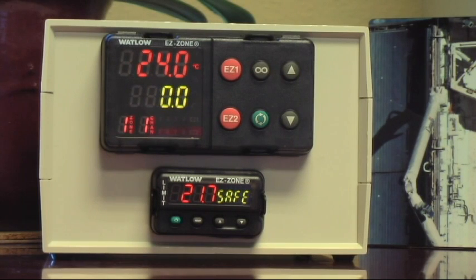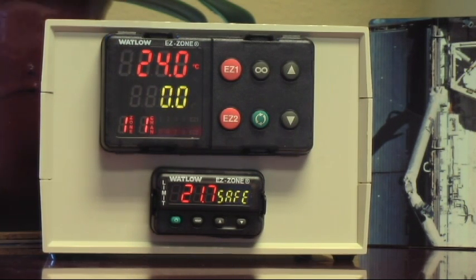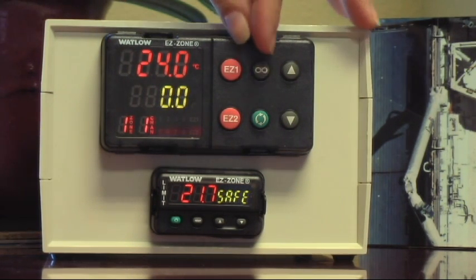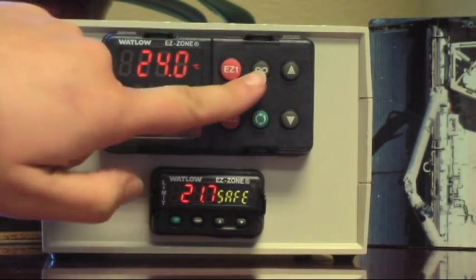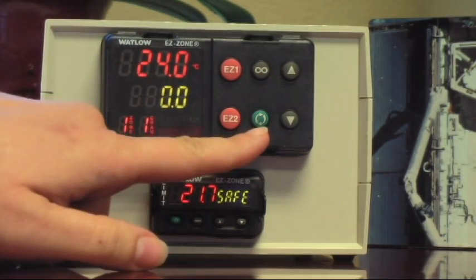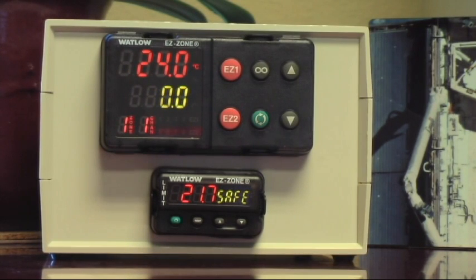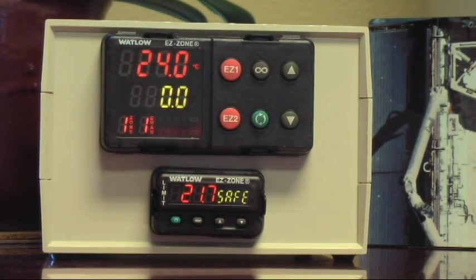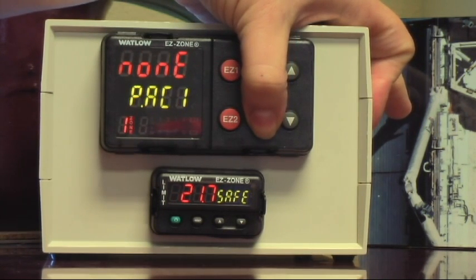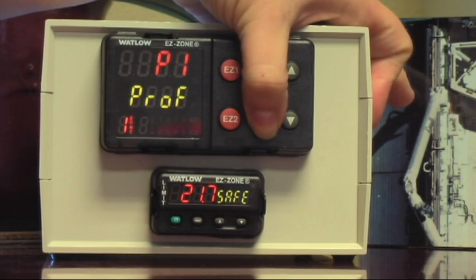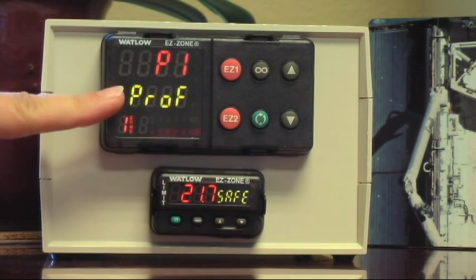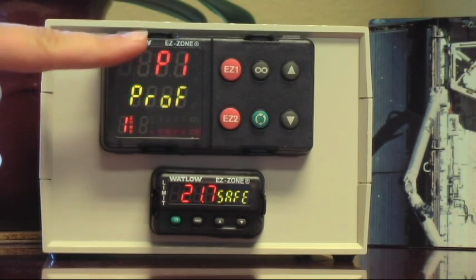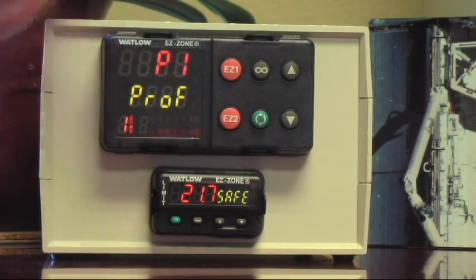This is going to be about a five-step profile and we can do it in just a few minutes. Ready? I'm ready. All right. First thing you want to do is we're going to start using these buttons right here. This is the infinity key and this is the advance key. So those are the buttons that you need to know for this setting. What we're going to do first is press the advance key for three seconds and that's going to take us into the profile mode. And there we go. We're in the profile mode and we're on profile one.